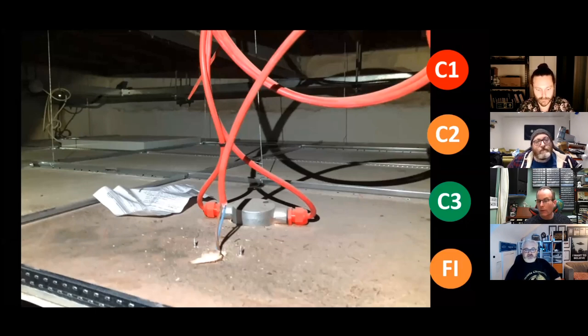So, yeah, no, these things can happen everywhere and anywhere. Totally unacceptable, to be perfectly frank. For me, I don't even like seeing red. I would prefer to see a steel braided copex coming from a piece of conduit supported along a piece of stud work that is deliberately fixed to support that. You'd have something like that that would actually allow some level of movement. And then a small 150mm loop or 300mm loop to allow movement of the tile. That's it. That's all they're getting.